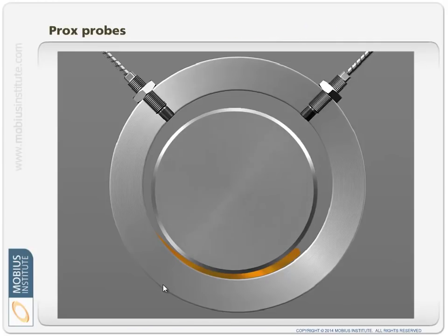Okay, so as a result of all of this, as I mentioned, we install two proximity probes, and they act as, you know, a form of triangulation to say where the shaft is at any time. Now, they are typically 90 degrees apart. You can, in most systems, compensate if those probes aren't exactly 90 degrees. There might be physical reasons why that couldn't be done.